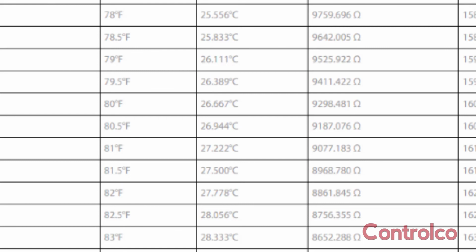Figure out the scale. So figure out what kind of sensor you have. Then go ahead and put your meter on it. Get the ohms value. Go to the chart, look it up, and then have a reference probe that you're looking at, a reference meter, something that's calibrated, and verify that the two numbers match or the two numbers are relatively close. If they aren't, then you just go into your controller and you make an offset change.